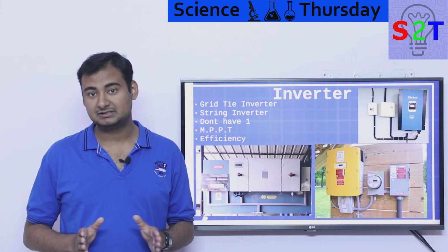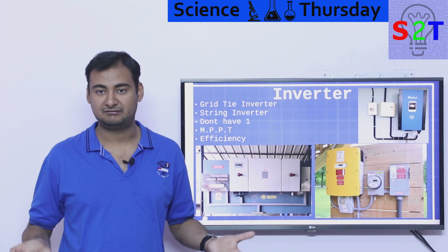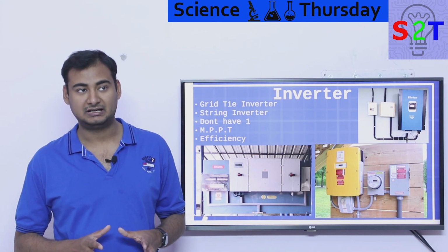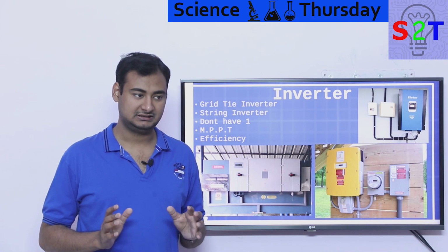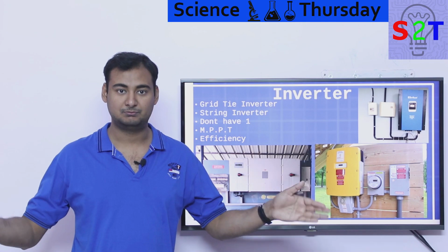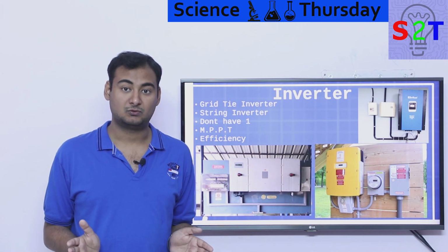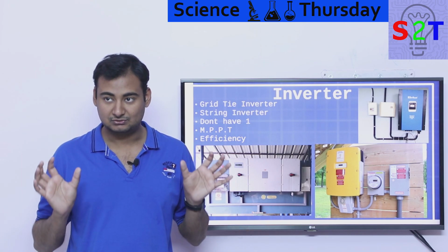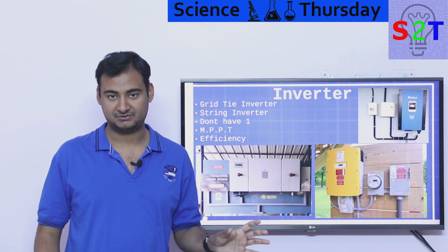And obviously, let's say you have a farm, let's say it's 500 kilowatts or 50 megawatts. Do not have few inverters. Try to have an appropriate number of inverters. Never have one inverter. Let's say you built a farm, and there are inverters that are 1 megawatt capable. Don't buy that. Buy 250 kilowatts. So in case of failure, you have at least 50% production.